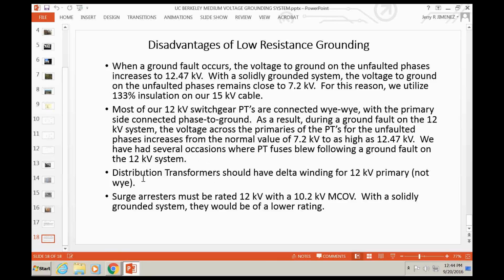Yeah. Okay, the third point here, very similar to the point I just made: distribution transformers on the 12 kV system should have a delta winding for the 12 kV primary and not a Y, for the same reasons as was mentioned in the step above. You get an overvoltage on the unfaulted phases if you have a grounded Y connection. And then the last issue is that the surge arresters must be rated 12 kV with a 10.2 kV MCOV. It stands for maximum continuous operating voltage. If we had a solidly grounded system, then these arresters would be of a lower rating.